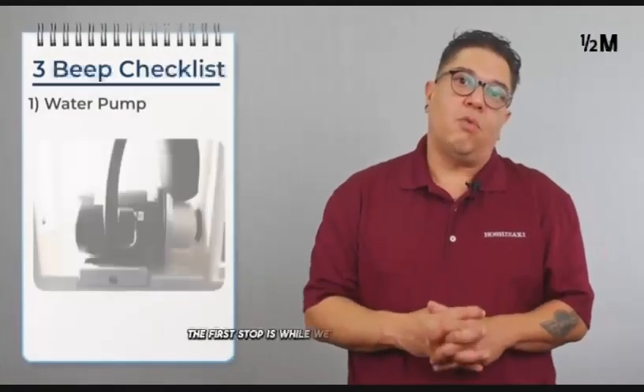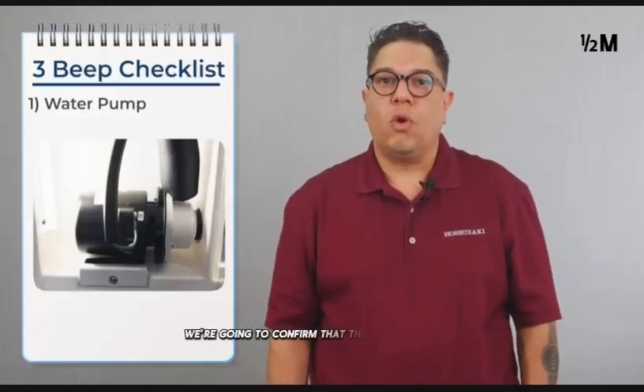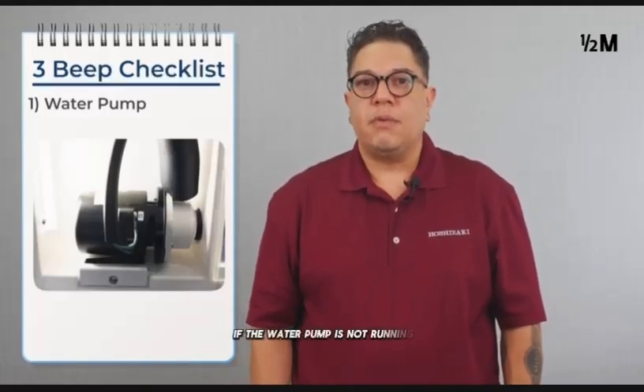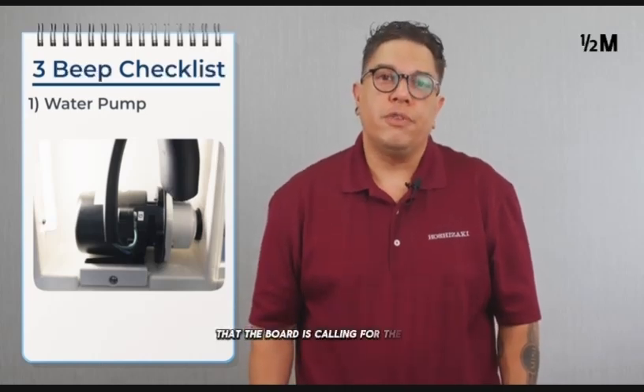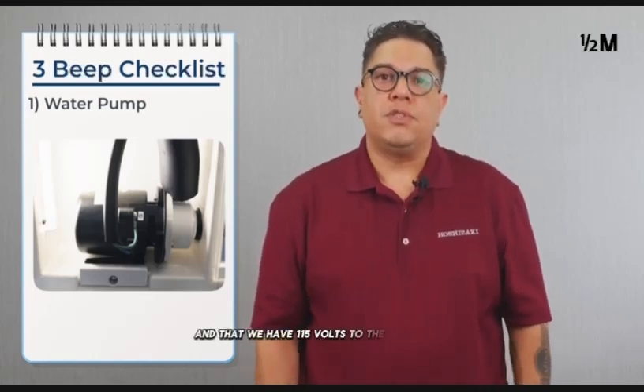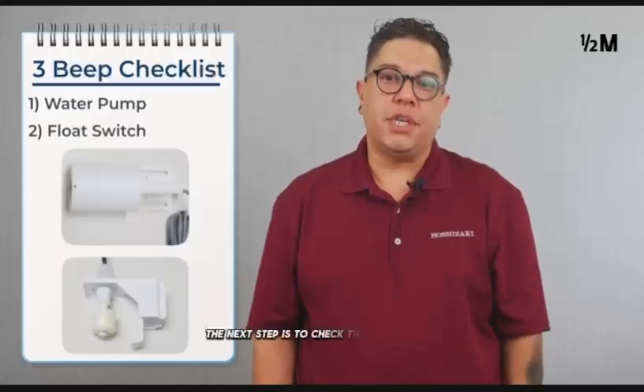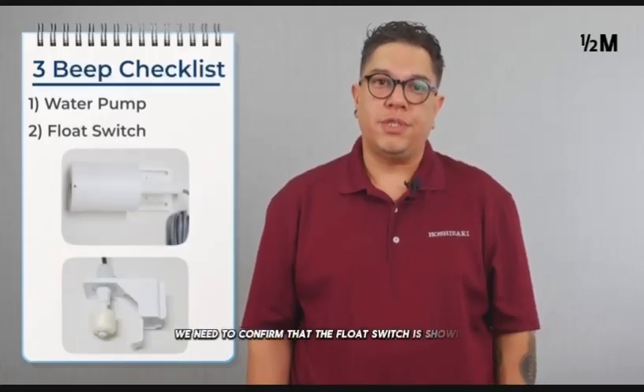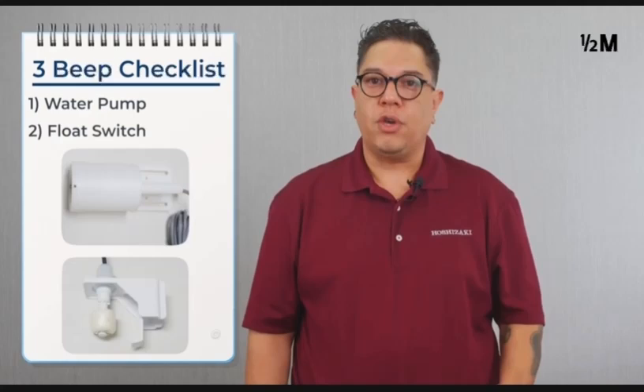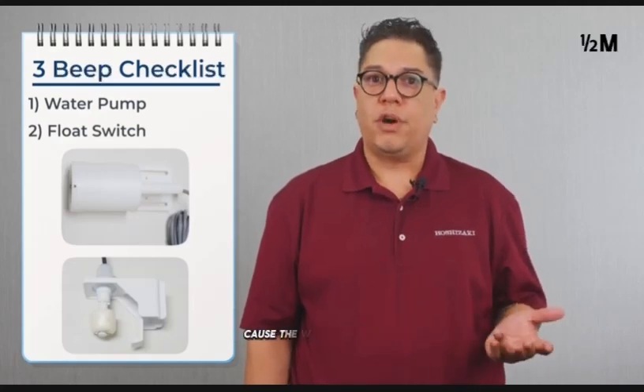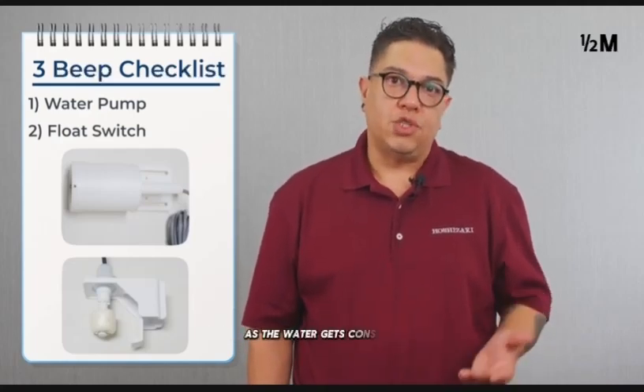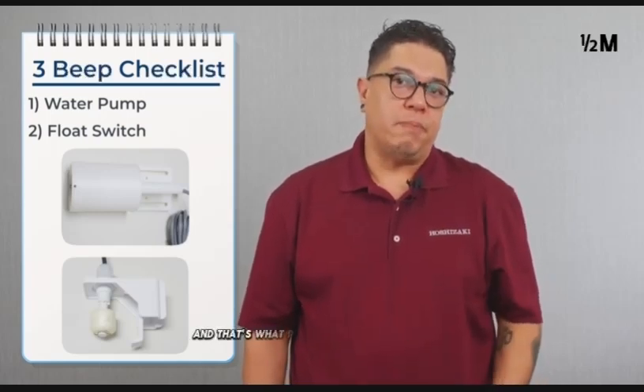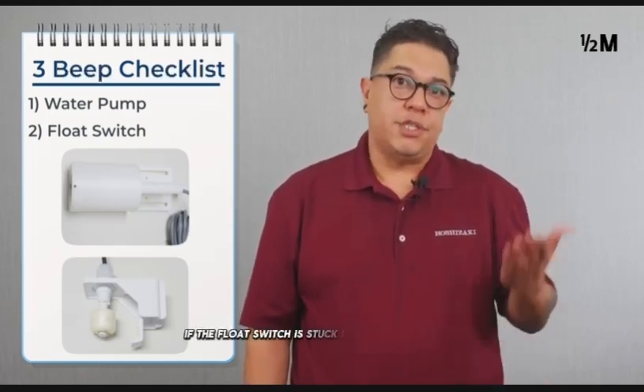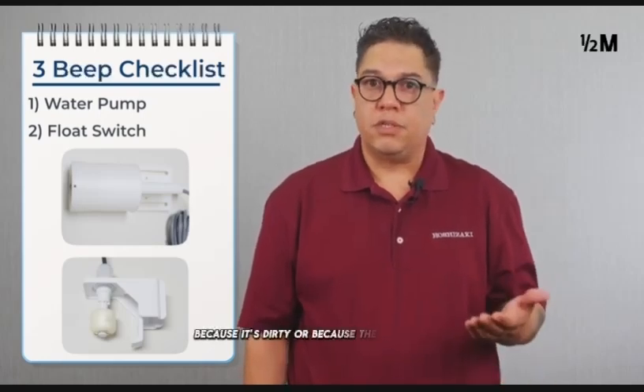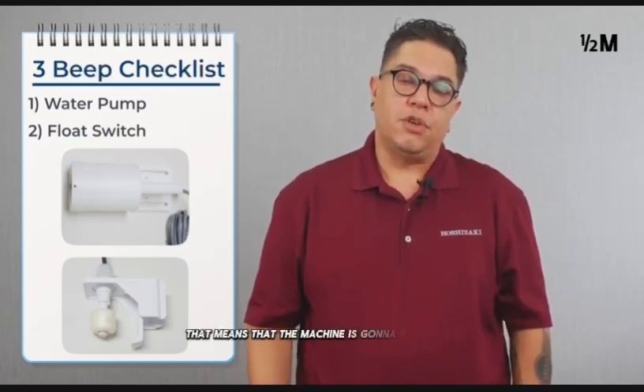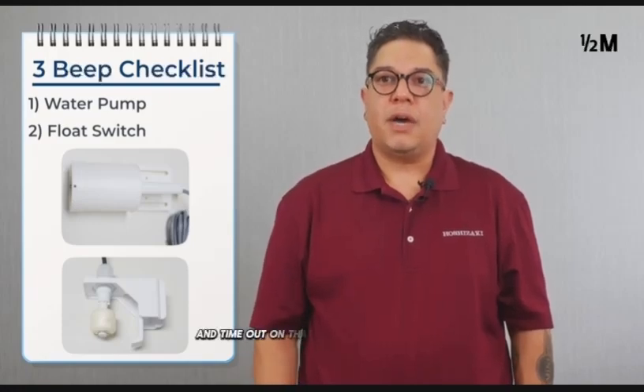The first stop is while we're running the machine, we're going to confirm that the water pump runs. If the water pump is not running, we need to confirm that the board is calling for the pump and that we have 115 volts to the water pump. The next step is to check the float switch. We need to confirm that the float switch is showing open and closed. During the freeze cycle, the float switch is in the closed position because the water tank is full. As the water gets consumed, the float switch shows open, and that's what puts the machine into harvest. If the float switch is stuck in the closed position because it's dirty or because the switch is bad, that means that the machine is going to run a long freeze cycle and time out on that 50 minutes on the board.